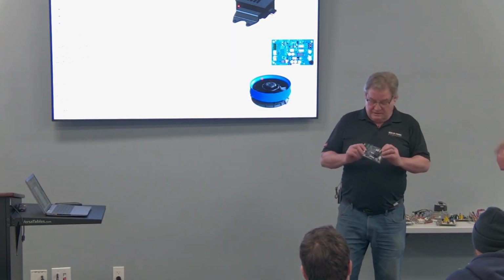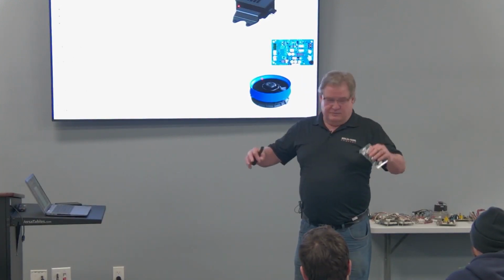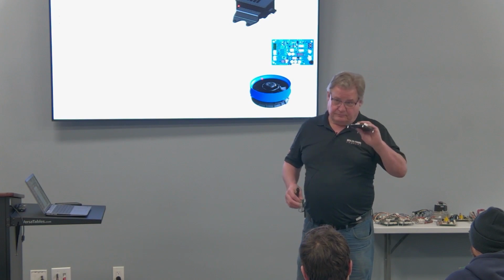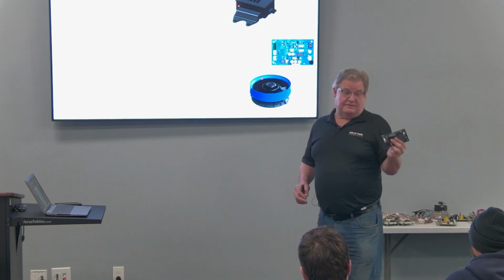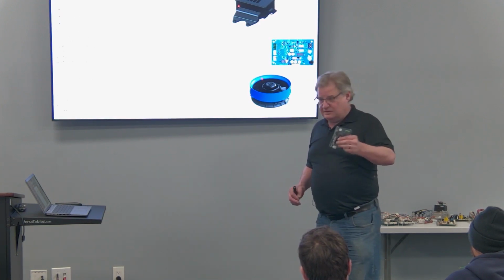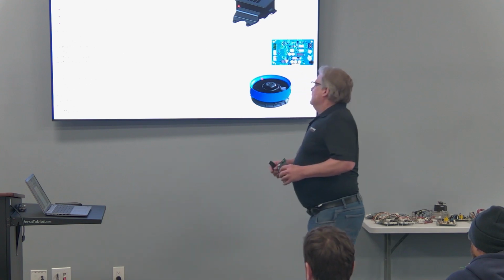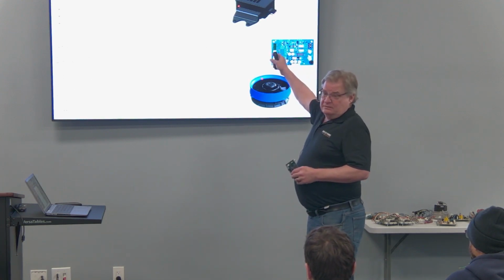Okay, this is already installed in the rooftop unit. So you set the rooftop unit, this is already there. However, there's a test you're going to have to go through with it. Okay, this is a required test. We'll talk about that. So the sensor's pre-mounted. We'll see in a minute where that is.